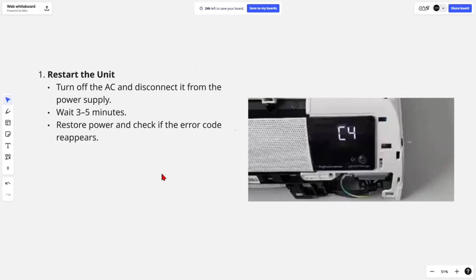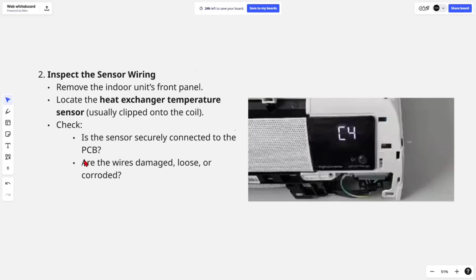Step 2, inspect the sensor wiring. Remove the indoor unit's front panel, then locate the heat exchanger temperature sensor, usually clipped onto the coil. Check: is the sensor securely connected to the PCB? Are the wires damaged, loose, or corroded?